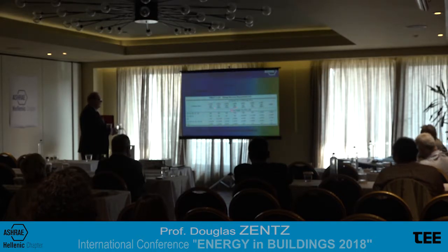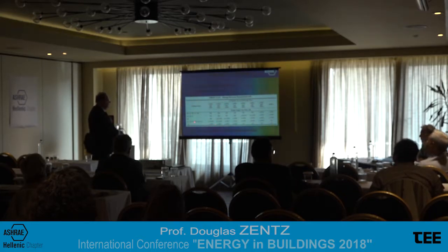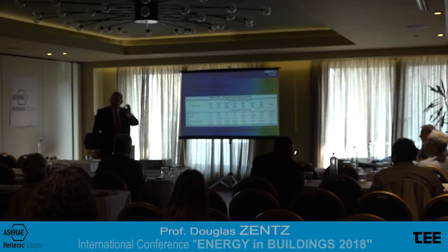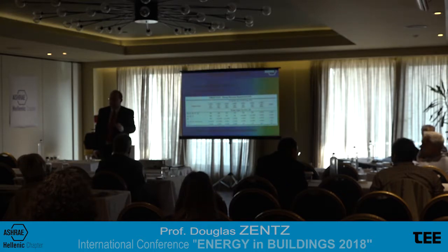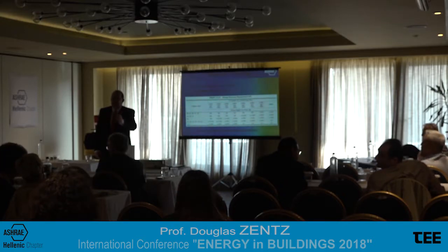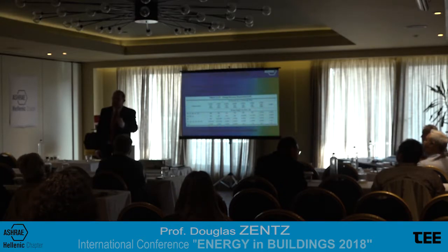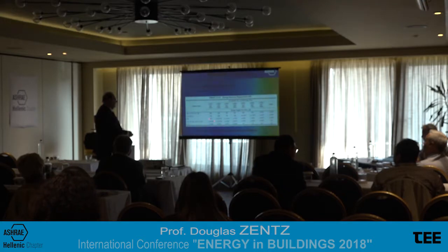This is also coupled with that. And it does have something to do with the standard. You said you're 3A, okay? If you're 3A, you're right here. This says if you've got, let's say, 12% outside air, not real big, 12%, it means that you have to have energy recovery on your air handlers if you're over 30,000 CFM.